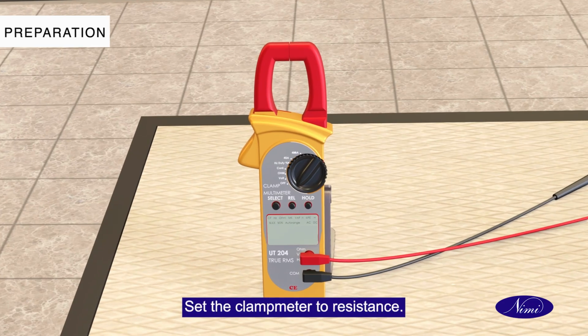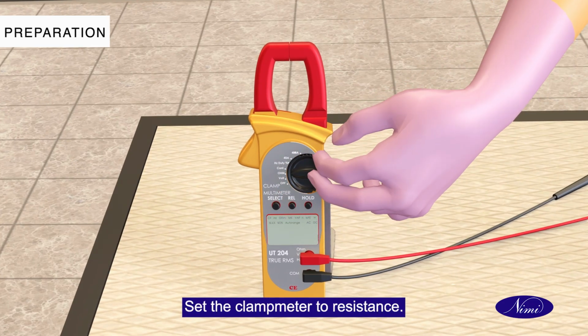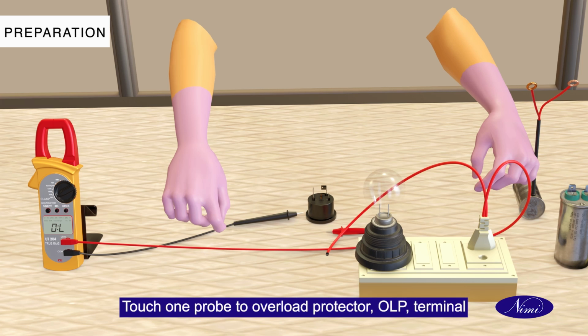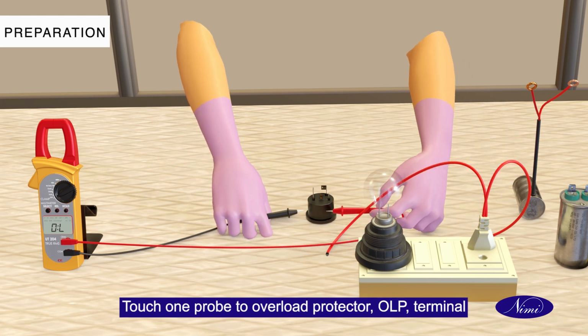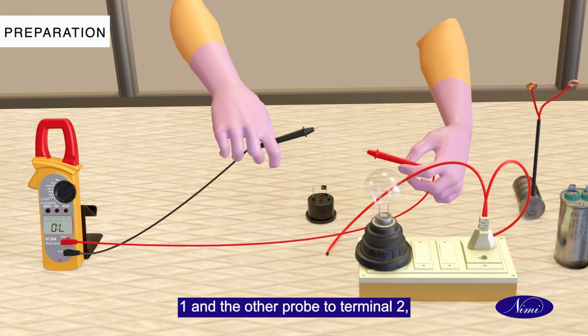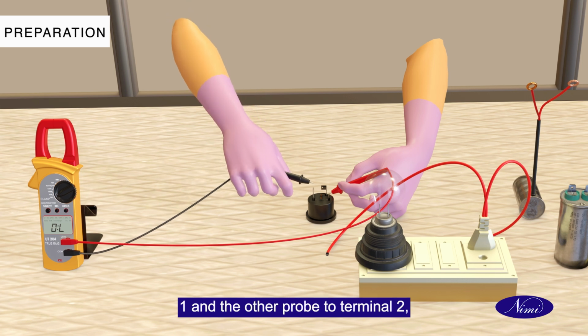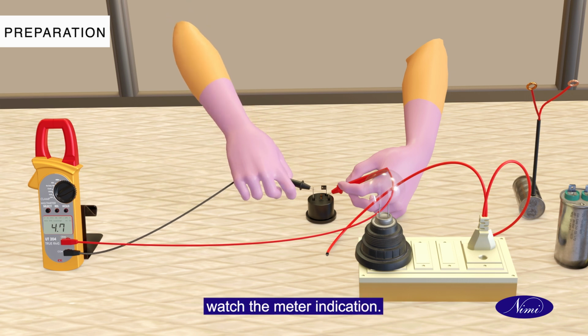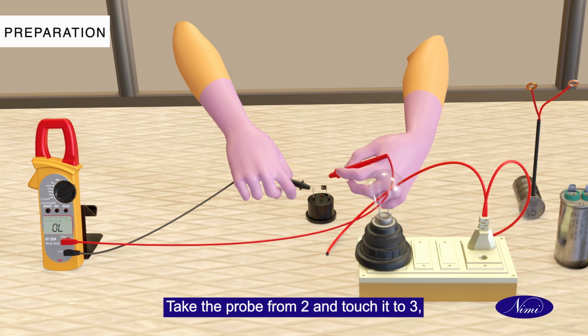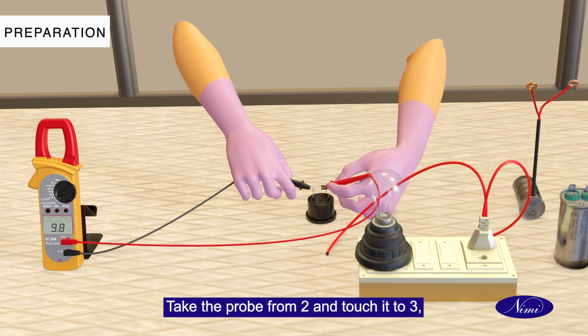Set the clamp meter to resistance. Touch one probe to overload protector OLP terminal 1 and the other probe to terminal 2. Watch the meter indication. Take the probe from 2 and touch it to 3. Watch the meter indication. If the clamp meter shows continuity, the overload protector is good.